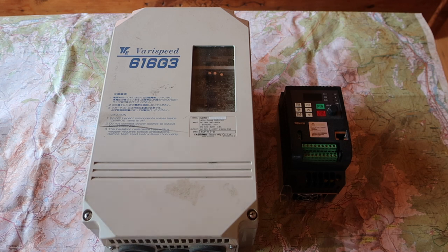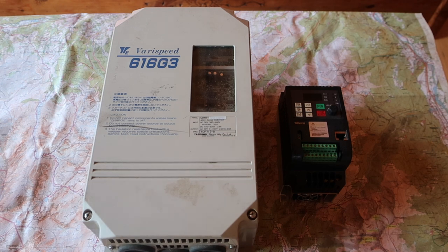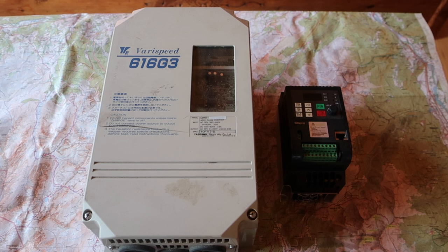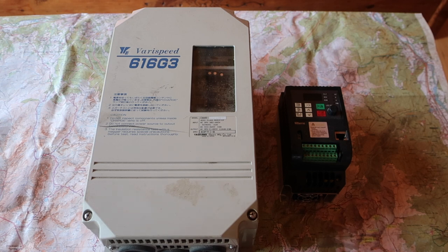The price and size of VFDs has come down significantly. However, I don't trust this to run at 2.2 kilowatts. Kilowatt and a half, probably. 2.2 kilowatts is not going to be long for this world. There is a significant difference in size of components in these two devices.